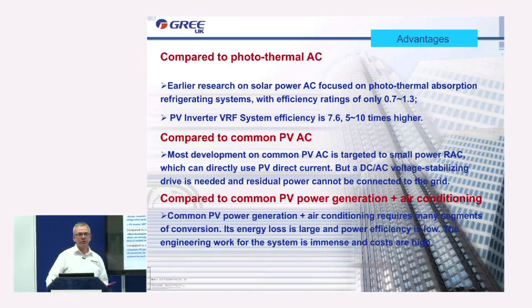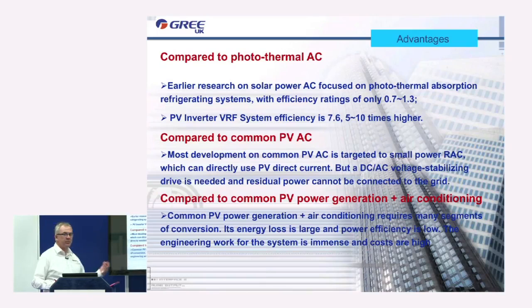Then there was some common PV connected to AC before, mainly only used, however, on smaller air conditioning systems. And the reason being for that, because there was some smaller units developed that could directly use the DC voltage as we do here. But because it could only be limited to low power, it was never really a cost-effective option, because obviously the cost of a small unit didn't really warrant buying large PV array installations. And the big problem they had with these as well, additionally, which of course I've already mentioned we don't have, is that you could not connect it to the grid, because they had no management way of controlling that.